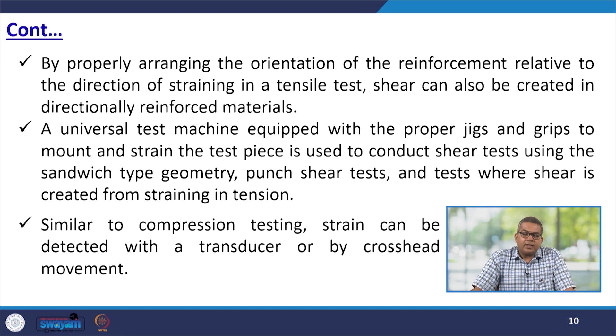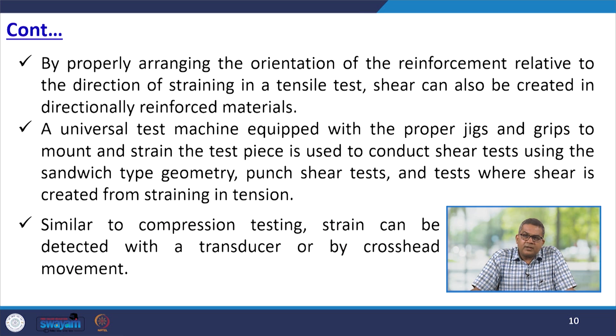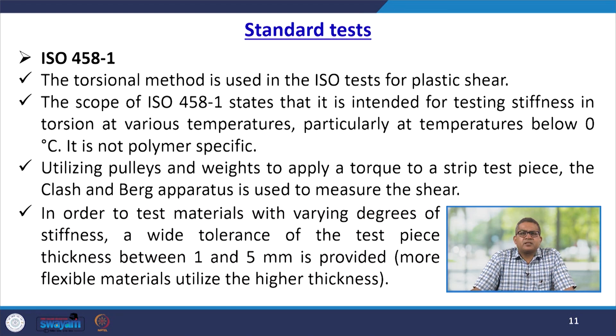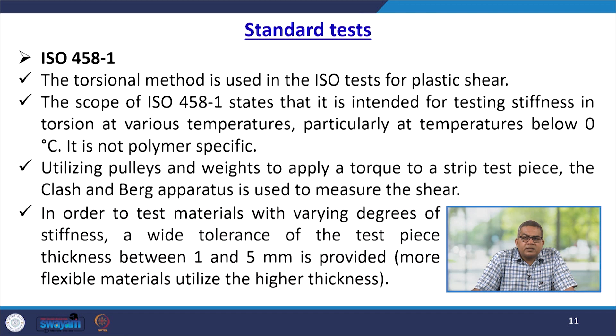A universal testing machine, sometimes referred to as a UTM, is equipped with proper jigs and grips to mount and strain the test piece. It is used to conduct the shear test using sandwich-type geometry, punch shear test, and tests where shear is created from straining in tension. Similar to compression testing, strain can be detected with a transducer or by cross-head movement. One relevant standard is ISO 458-1; the torsional method is used in this particular ISO test for plastic shear. The scope of ISO 458-1 states that it is intended for testing stiffness in torsion at various temperatures, particularly at temperatures below 0 degrees Celsius. It is not polymer specific.